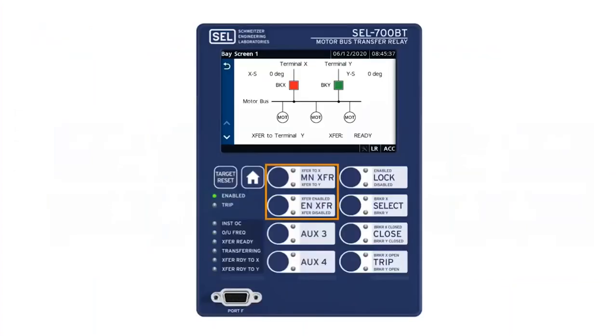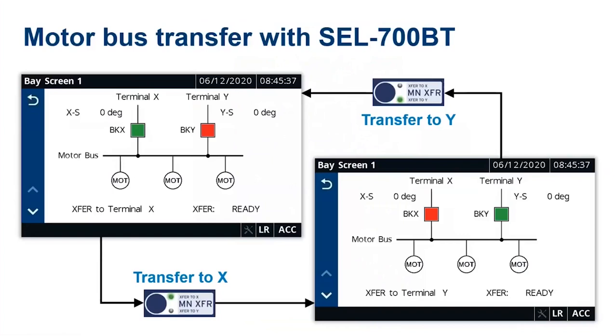They are also included in the instruction manual CD. Okay, so we have two in the default settings of the relay. We have these two buttons dedicated to enabling and disabling the transfers and to manually start the transfer. Basically, you would use this push button to enable it using the default settings, of course. And then by pressing the button above that, you go from one feeder to the other.